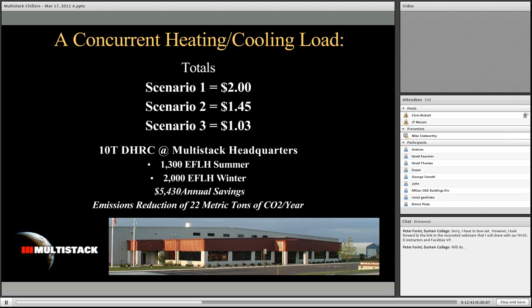As an example, the type of building that Multistack has in Sparta really probably could have been done with package units, rooftop package units, but in fact we installed chilled water so that we can demonstrate heat recovery. And we have a 10-ton heat recovery chiller at the Multistack headquarters. We run it about 1,300 equivalent full load hours in the summer and about 2,000 equivalent full load hours in the wintertime. And that saves us about $5,000 a year, and that's about 5,000 therms of gas a year. So quite a bit of savings.